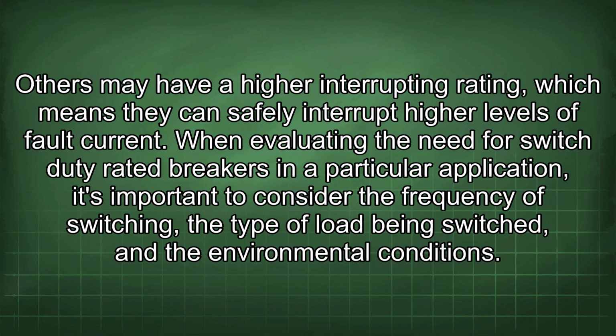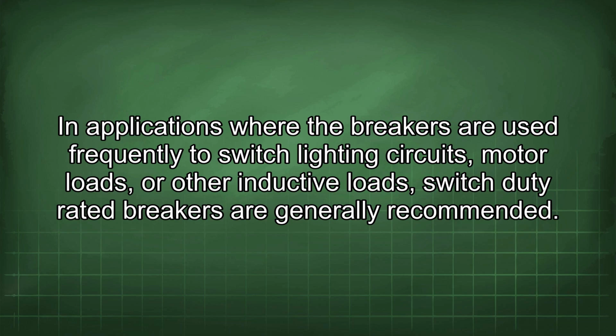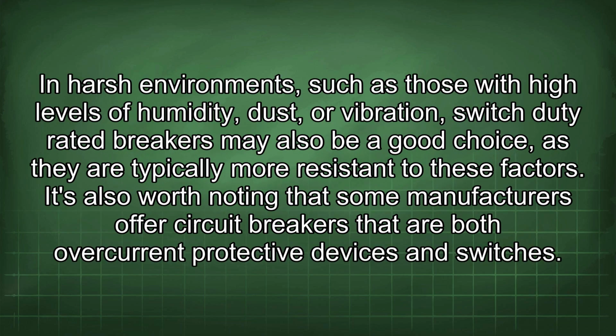When evaluating the need for switch-duty rated breakers in a particular application, it's important to consider the frequency of switching, the type of load being switched, and the environmental conditions. In applications where the breakers are used frequently to switch lighting circuits, motor loads, or other inductive loads, switch-duty rated breakers are generally recommended. In harsh environments, such as those with high levels of humidity, dust, or vibration, switch-duty rated breakers may also be a good choice, as they are typically more resistant to these factors.